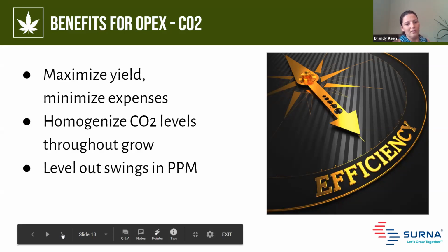You could do some modulation instead of just having it come on at 1200 and turn off at 1500, staying at 1400 all the time — you could modulate CO2 valves with a more sophisticated system to achieve that. I'm not sure it has enormous benefit, except maybe after the lights go off, to make sure you haven't overshot what you absolutely need. But it is something that's doable.